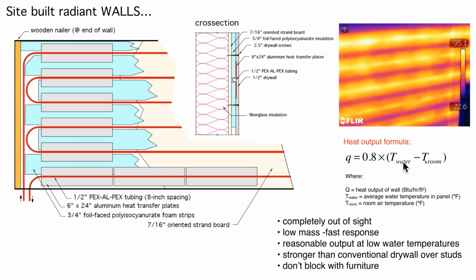Now, you'll see this is the same type of formula as before, but it has a different number here. The radiant ceiling, that number was 0.71. For a wall, it's 0.8. We actually get a little more convective output from a wall because it's a vertical surface. We do get some warm air rising from that, and that enhances the total heat output. So we have both radiant output and convective output. If we are working with 110 degree average water temperature in a 70 degree room, again, our difference would be 40 times 0.8. We're getting 32 BTUs per hour per square foot.